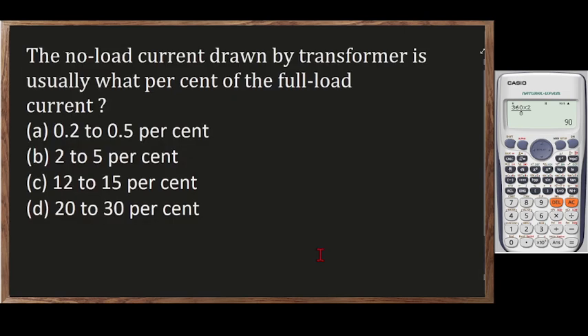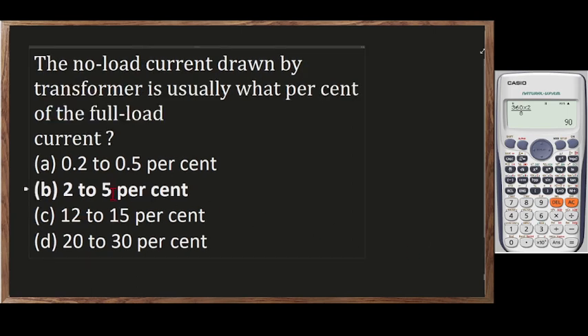The no load current drawn by the transformer is usually what percent of the full load current? No? So, the correct answer for this one is letter B, no? 2 to 5%. So, kaya yung ating transformer efficiency is from 98 to 95%. So, medyo mataas-taas yung efficiency ng ating transformer, no?